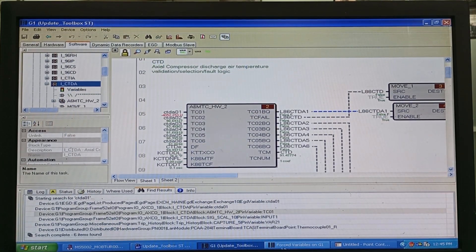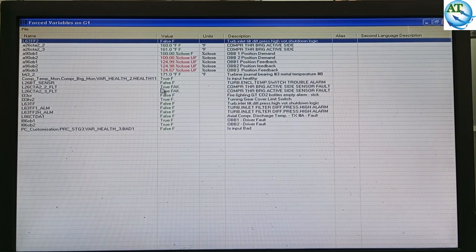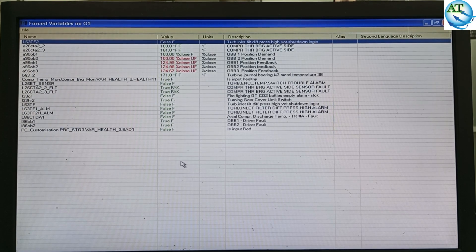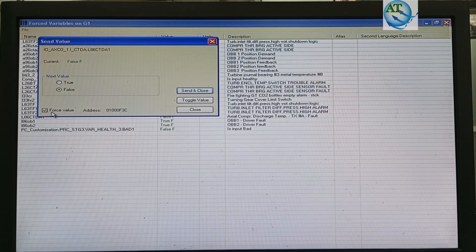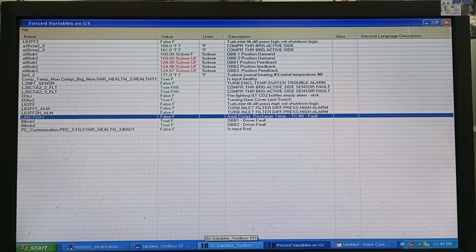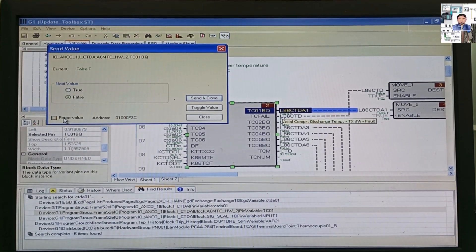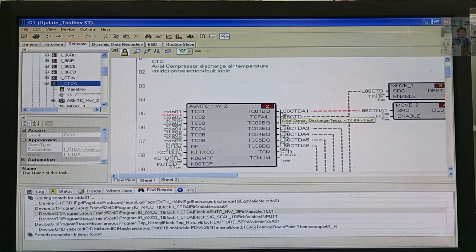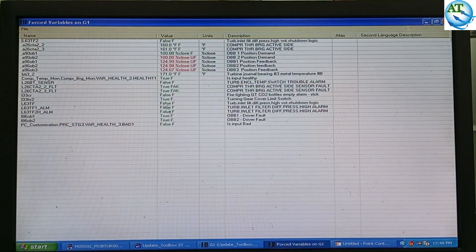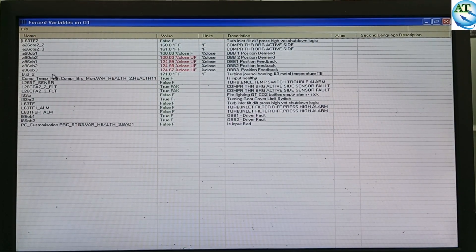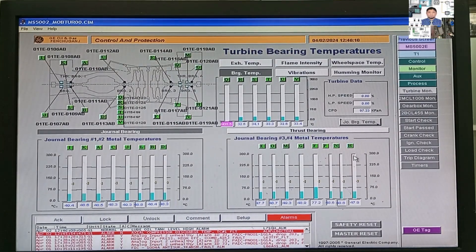Now I want to force from the block system. I am forcing it again — you can see it is showing the force. In the list, you can find the forcing variable. Now I will unforce it from the logic system. Previously I unforced it from the variable system; now I will unforce it from the block diagram system. Right-click on the block, select Remove Force Value, and press Send and Close. It will become the normal value. After unforcing, in the list, no forcing values are showing.